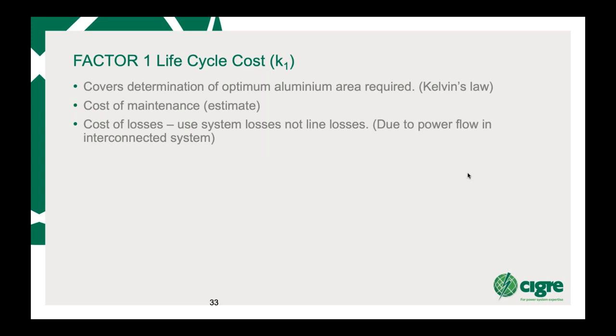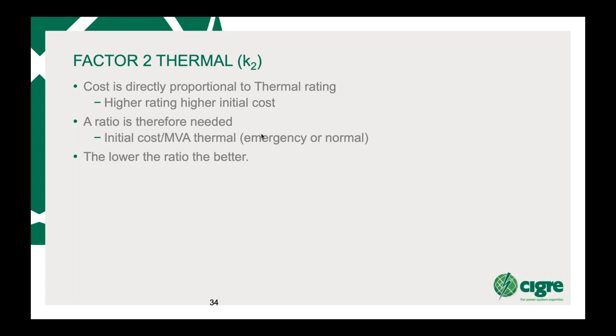And the first one really that we're looking at is the life cycle cost. So we take the life cycle cost, which covers the determination of optimum aluminium area, cost of maintenance, and cost of losses. Now, normally you'll find the cost of maintenance is minimal over the life of the line. The cost of system losses is really where you get a very large amount in the life cycle cost. The second factor that you would look at is the thermal rating.